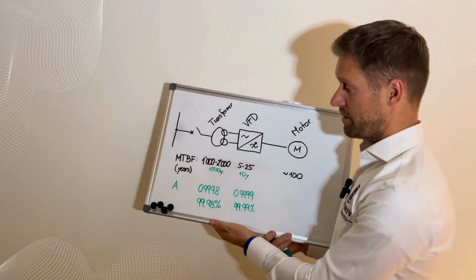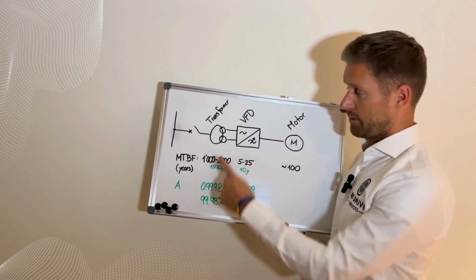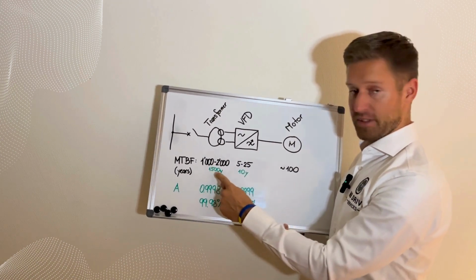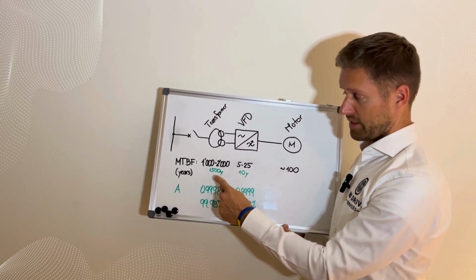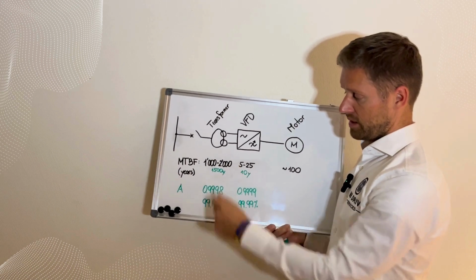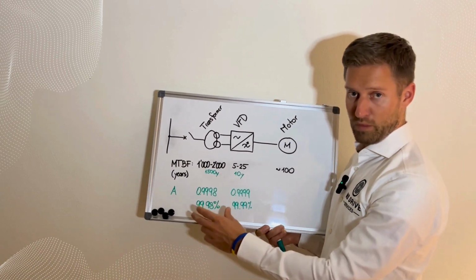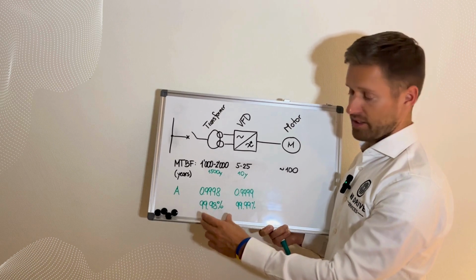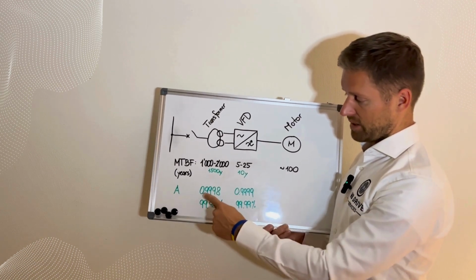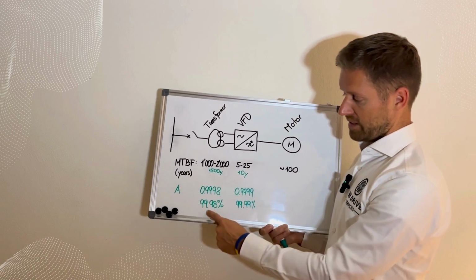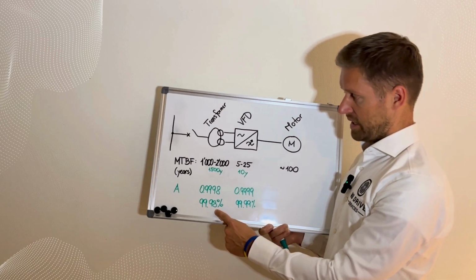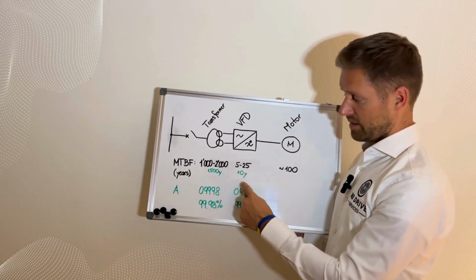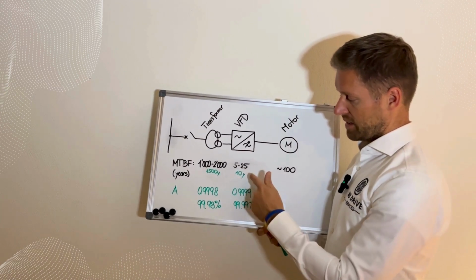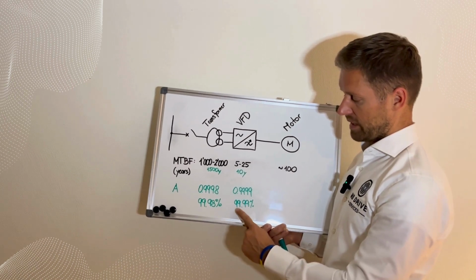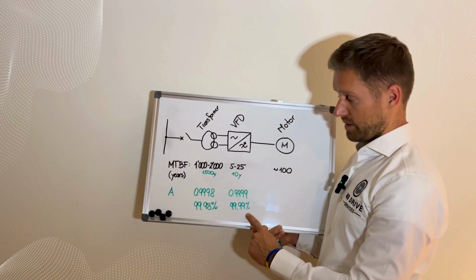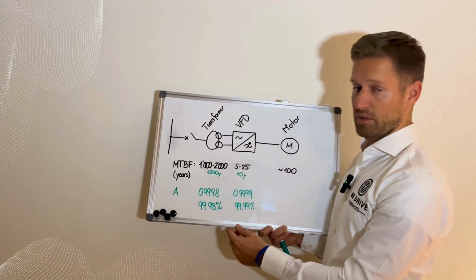So looking now at the availability of the system components, if you look at the transformer, I have considered 1500 years mean time between failures. So I took something in the middle, and I was considering this 4 months period, the MTTR, mean time to repair. Then I'm getting availability 0.9998, so 99.98%. If I take the VFD and I would consider 10 years MTBF and 6 hours MTTR, time to repair, then I'm getting 99.99%, so even higher than the transformer, the availability.